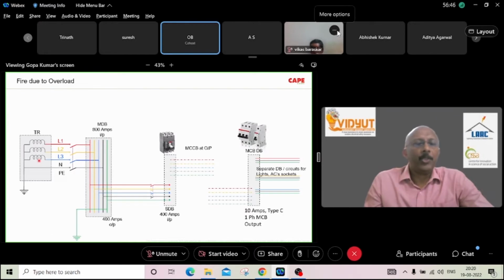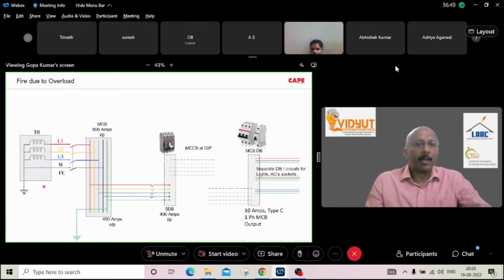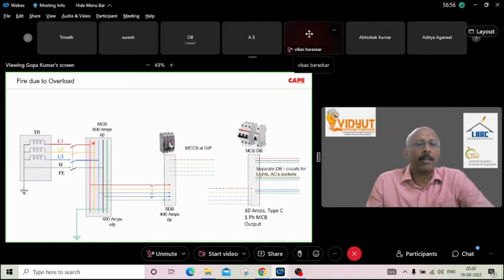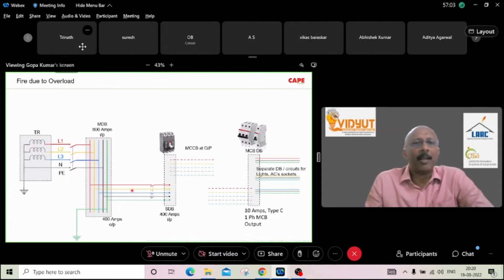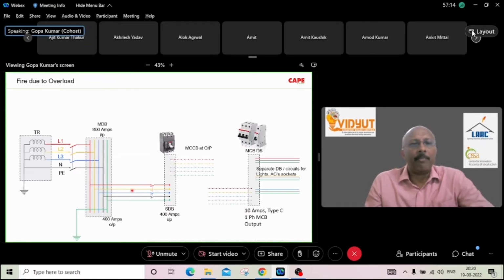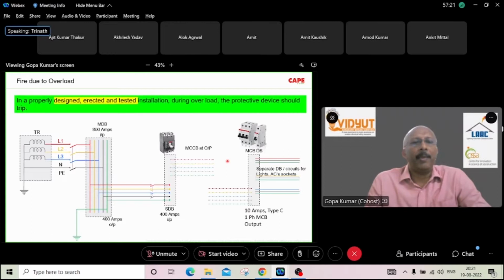Sorry. So we should understand that each of our electrical wiring has a protective device. Let's say, for example, in a hospital, there is a transformer, there are protective air circuit breakers, MCCBs, MCBs, fuses, and so many protective devices in the circuit. The question to be asked is, once the ICU equipment is becoming hot, before creating a fire, why are these protective devices not disconnecting the supply? Why are they not tripping? If the device didn't trip, of course, the equipment catches fire. So it's very simple to understand. We should not say that fire is due to overload. We should say that fire is due to non-operation of the protective device. It's very easy.